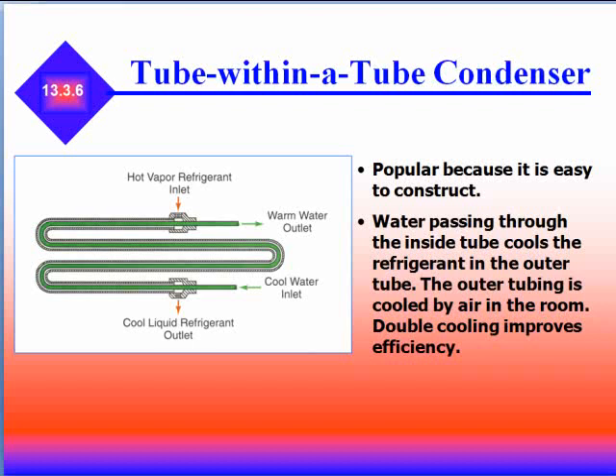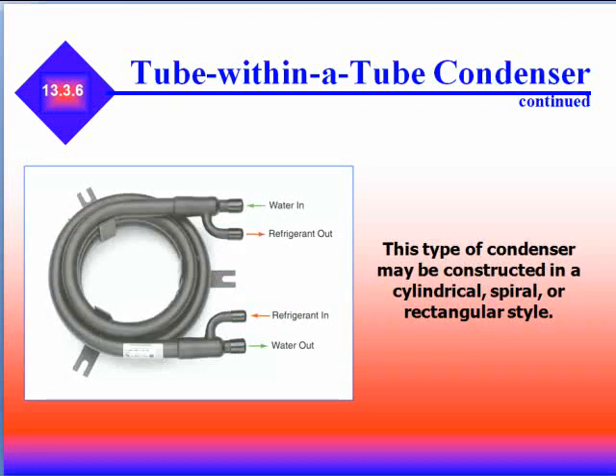In a tube-in-tube condenser, you'll notice the cool water inlet is on the same side as the cool liquid outlet — meaning the water and the refrigerant are moving in opposite directions. This type of condenser may be constructed in a cylindrical, spiral, or rectangular style.